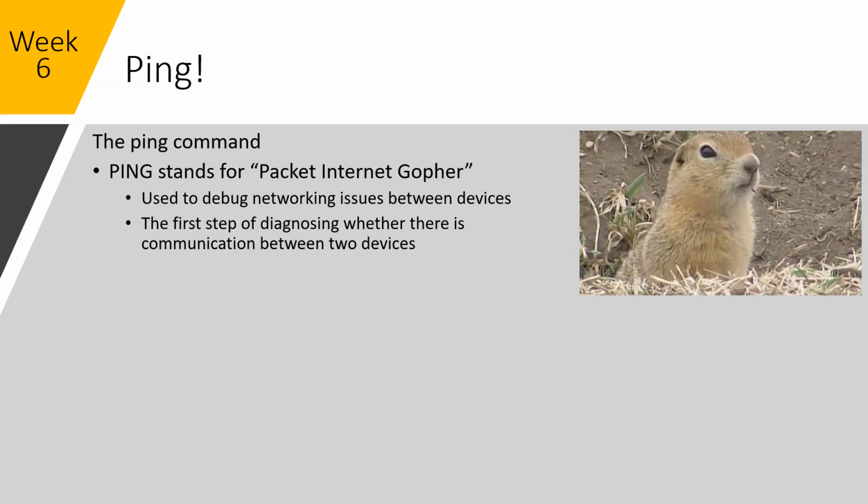If you don't know where a free IP address may be on a network, and you can get onto a machine that is already on the network and ping and get no response back from a specific address, there's a good chance that you can then set the IP address of your machine to that address and then be able to access the PLCs with your programming software.